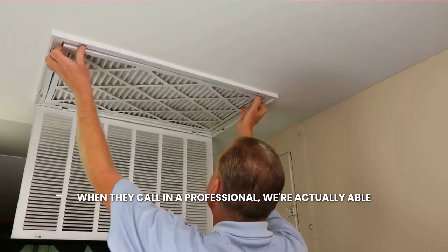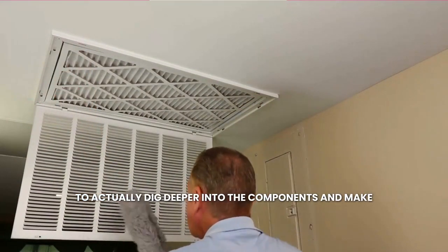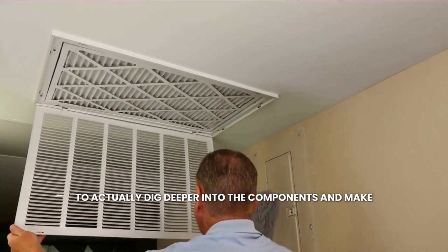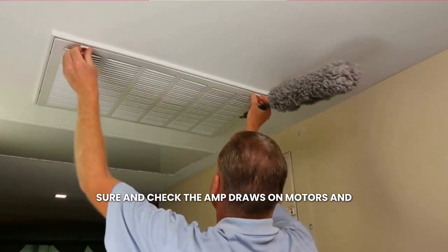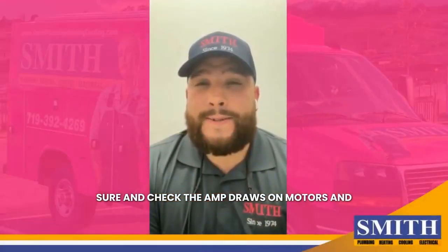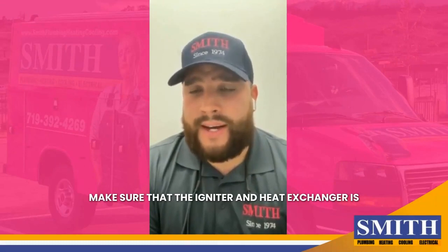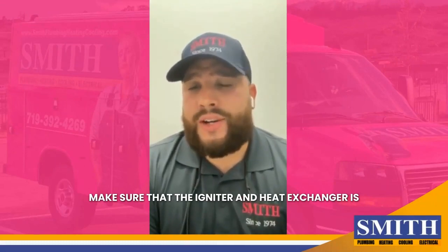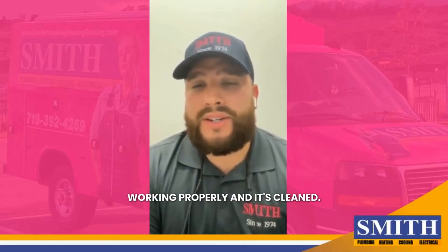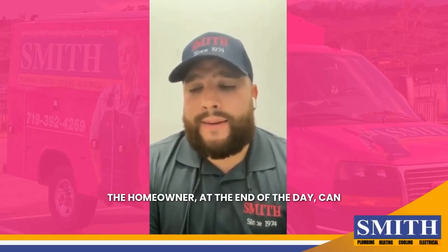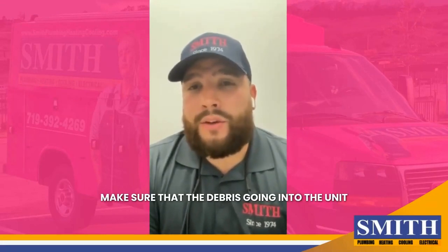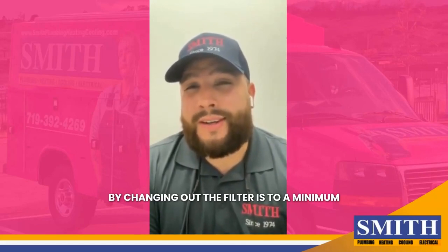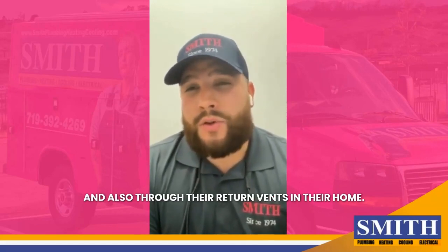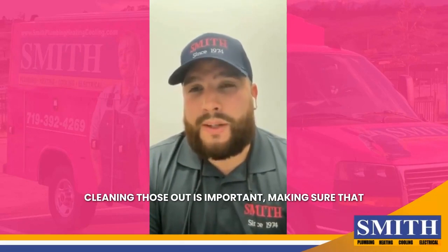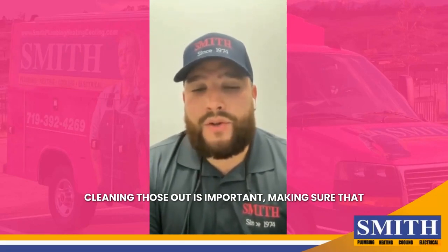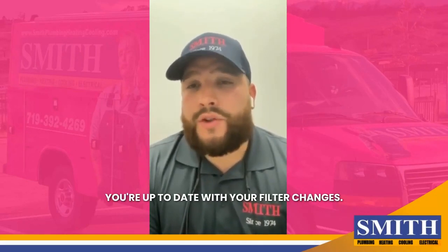When they call in a professional, we're actually able to dig deeper into the components and check the amp draws on motors, and make sure that the igniter and heat exchanger is working properly and is cleaned. The homeowner at the end of the day can make sure that the debris going into the unit is kept to a minimum by changing out the filter, and also through their return vents in their home. Cleaning those out is important, making sure that you're up to date with your filter changes.